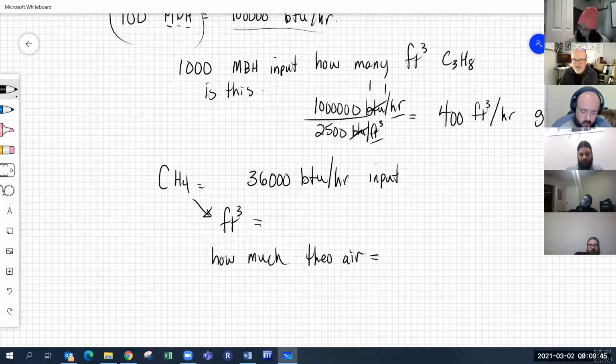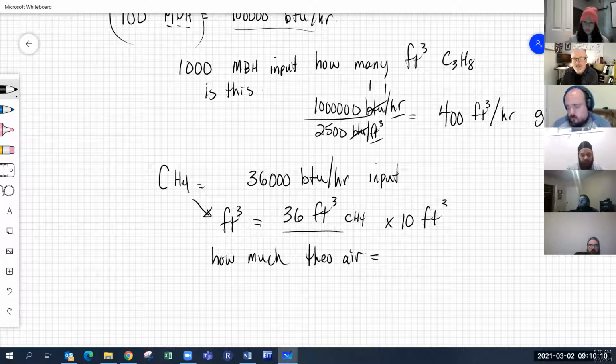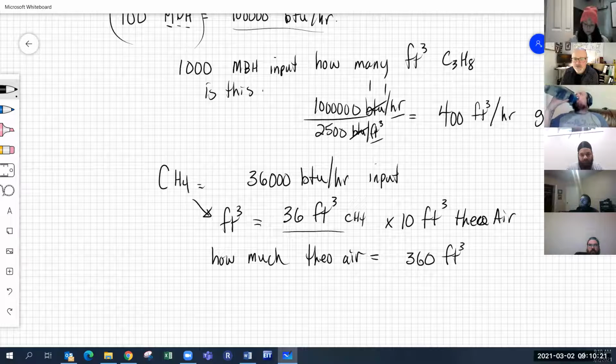So I want to know two things. I have 36,000 BTUs per hour input. How many cubic feet of natural gas is that, and how much theoretical air do I require? 36 cubic feet of natural gas and 360 cubic feet of theoretical air. So I have 36 cubic feet of CH4, and I know that I need 10 cubic feet of air for every 1 cubic foot of natural gas. So my theoretical air is 360 cubic feet per hour.